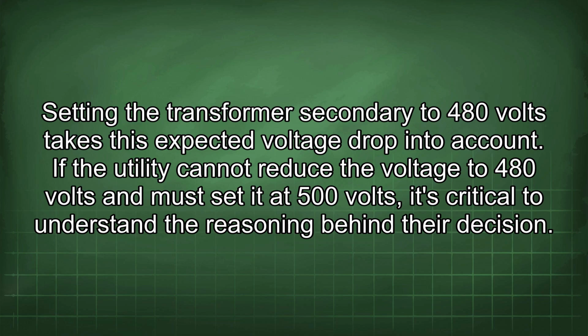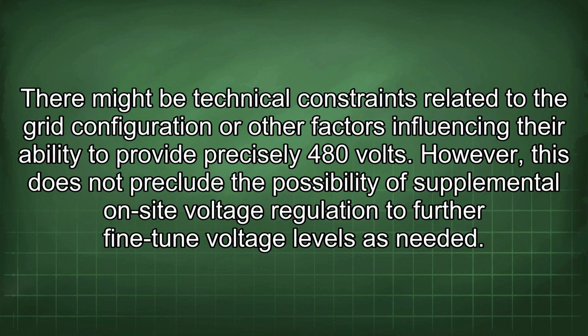If the utility cannot reduce the voltage to 480 volts and must set it at 500 volts, it's critical to understand the reasoning behind their decision. There might be technical constraints related to the grid configuration or other factors influencing their ability to provide precisely 480 volts.